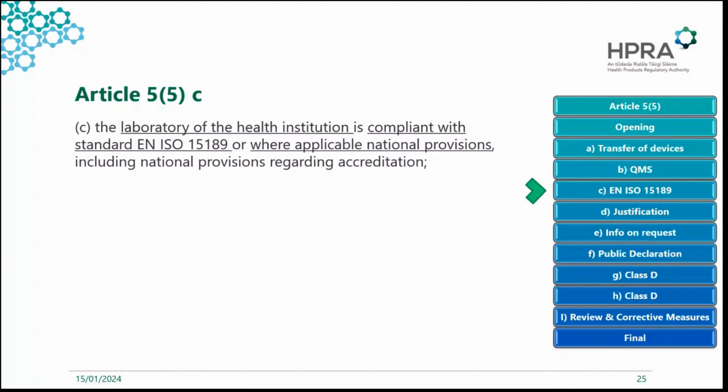And then on the topic of ISO 15189, point C talks about the laboratory of the health institution being compliant with standard EN ISO 15189, or where applicable national provisions, including national provisions regarding accreditation. So there's a few points we can talk through on this as well. First off, this mentions the laboratory of the health institution. So it doesn't mention the IVD or device. That means once the laboratory is compliant with ISO 15189, then that is sufficient to meet this requirement. There isn't a requirement for each individual in-house test to be within scope of that accreditation or compliance. It's just sufficient for the laboratory to be compliant. So that's one point to talk through.